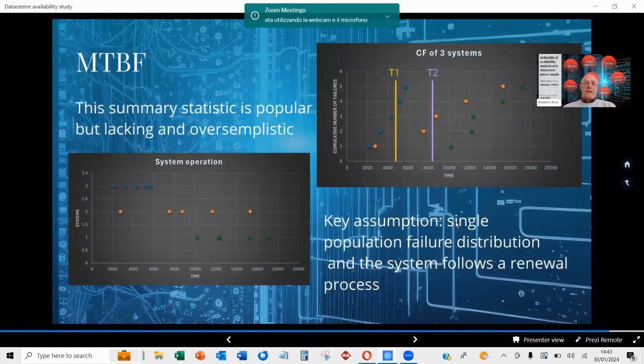Then there's MTBF. I'd like to connect this to the battery topic. When we looked at 435,000 hours, that was the worst case, so 50 years was the worst case. It's quite clear how you got to this number: by looking at a very large population of batteries, most of which are replaced in advance when the recharging criteria or functionality drops below target. It may happen that one or two batteries have actually failed, and those become the failed batteries out of a huge population. But that doesn't reflect the fact that batteries are replaced, and there's very little chance the battery will fail because it's replaced prematurely.